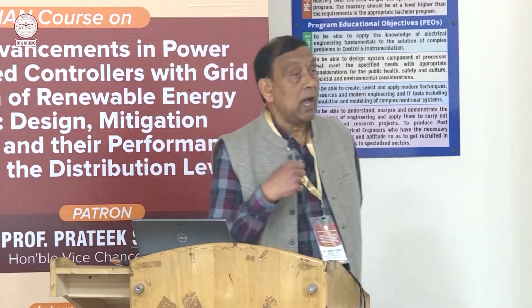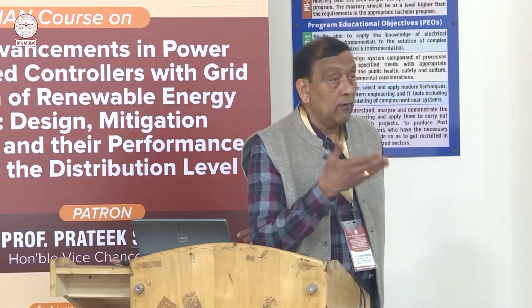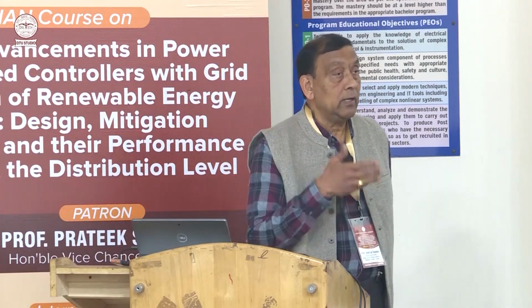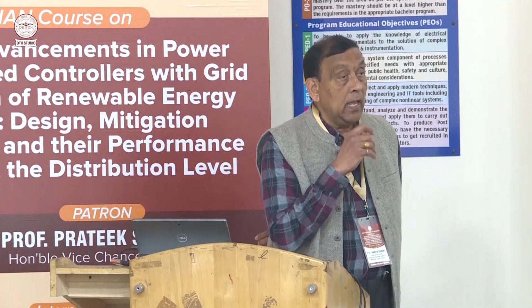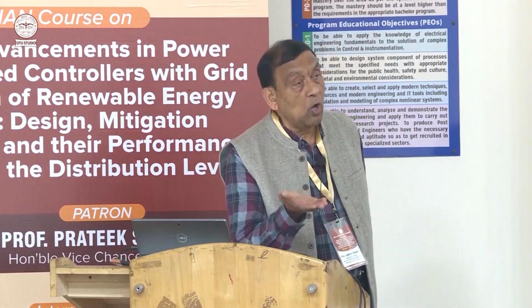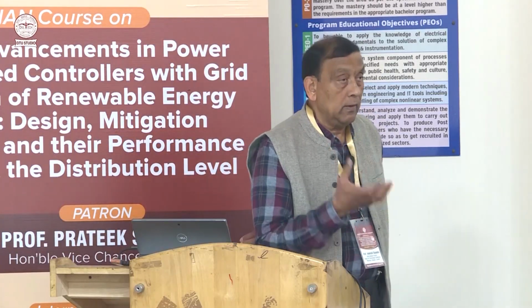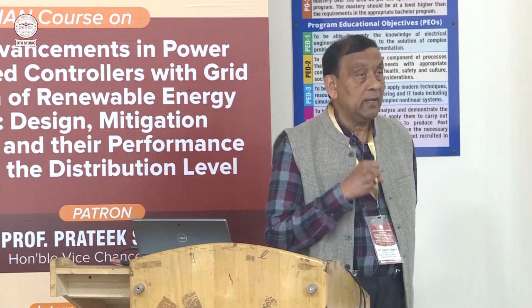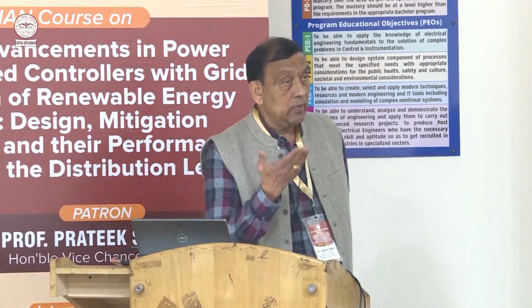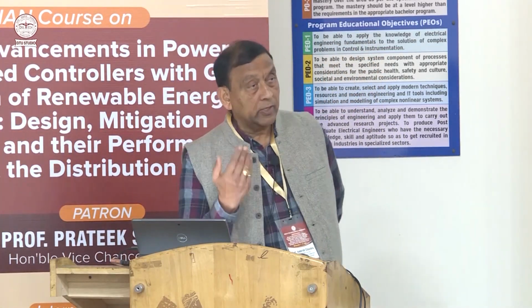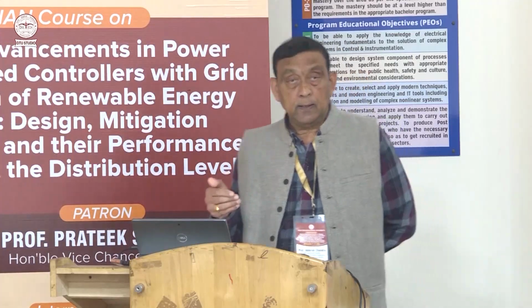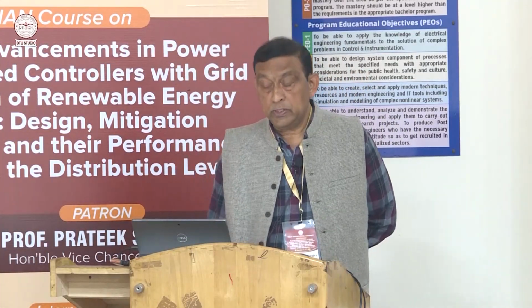because you are having harmonics, and the fifth harmonic, 7th, 11th, 13th, 17th, 19th, those harmonics are there, and then they will generate extra losses in the core, in the rotor and stator material because of the ferromagnetic losses, hysteresis losses, and the eddy current losses.